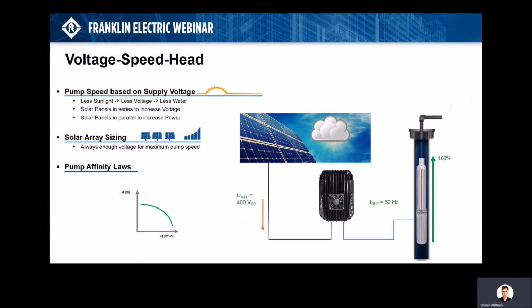What will happen is that the voltage will drop and your system will immediately reduce pump speed in order to keep running. That will reduce the amount of water you are pumping, but not only in a linear way. Due to the pump affinity laws, the pump head or pressure will be reduced by the square, which will then lead to a further reduction in water flow, since you will be running at a completely different pump operation point. If you haven't sized your system carefully, or if you are using low efficiency components, there will be the risk of running into a so-called dead head situation.